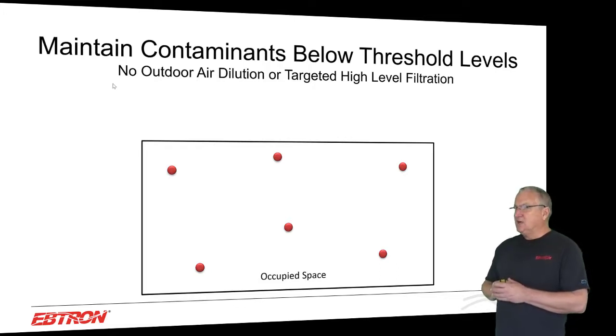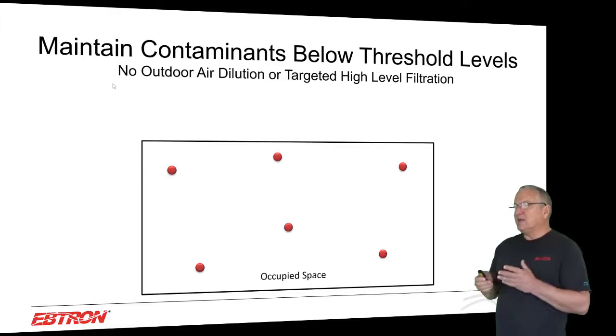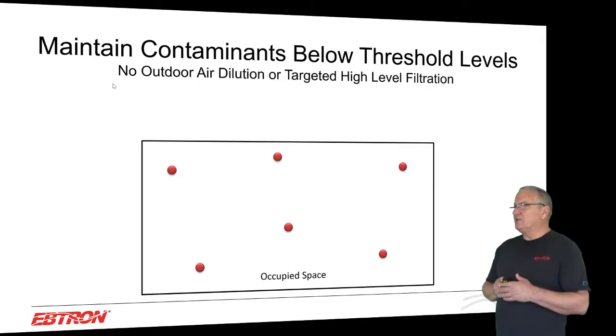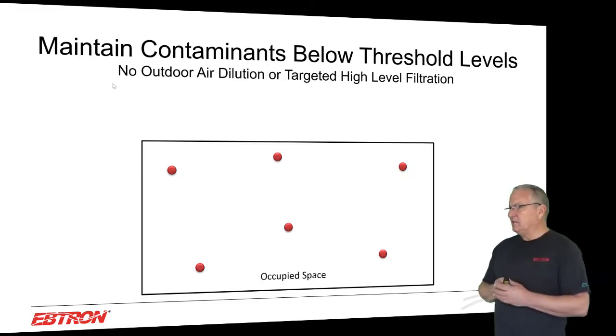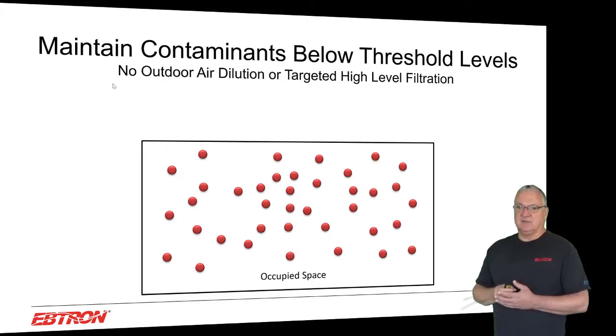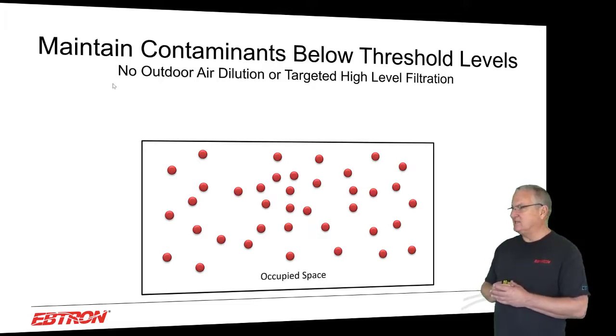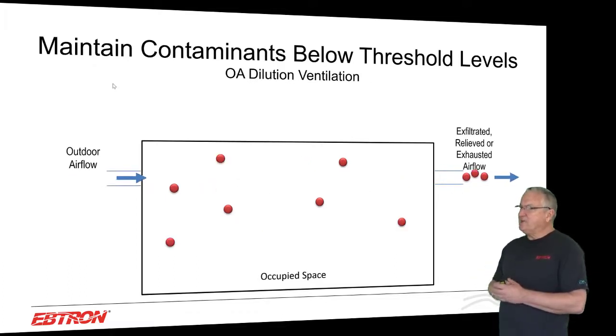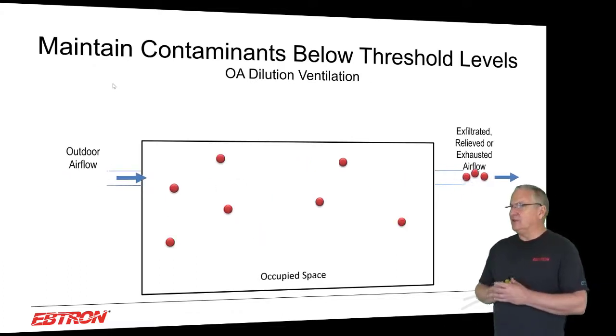In an occupied space, those red circles represent some type of contaminant — they could be COVID. You'll most likely go into a space and there will be some level of contaminants already there. If we have no outdoor air for dilution or any kind of targeted high-level filtration that can actually remove the contaminant, the contaminant level will just continuously increase. This is really the case today with COVID, particularly in residences, because we have no real requirements for outdoor dilution ventilation and very poor filtration in residences.